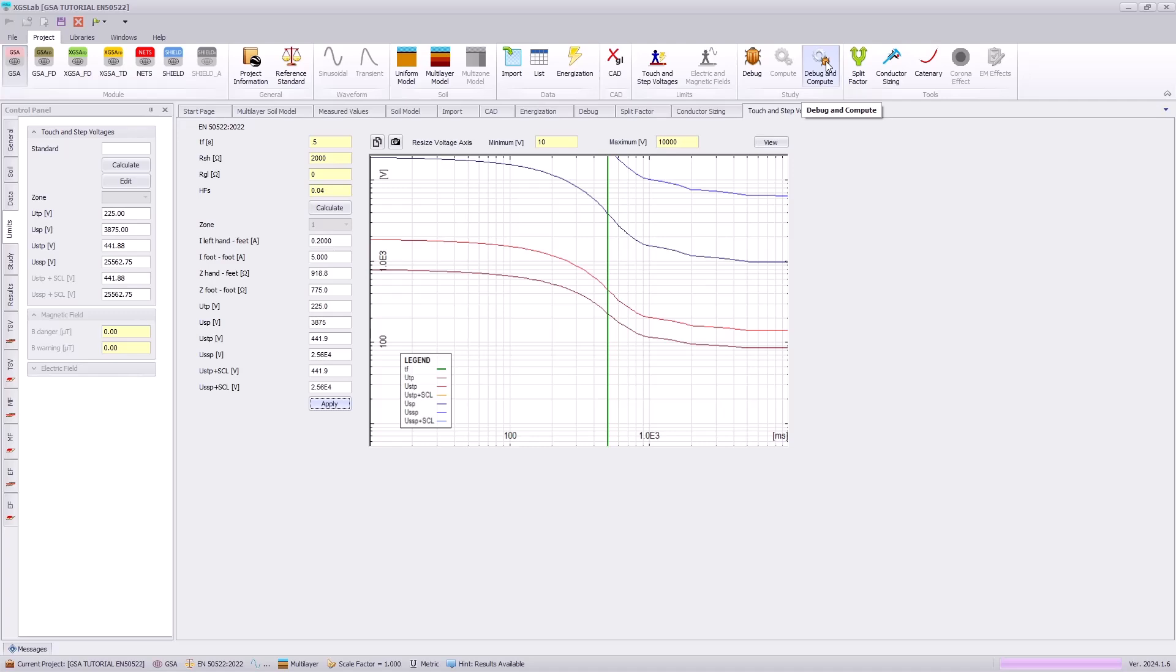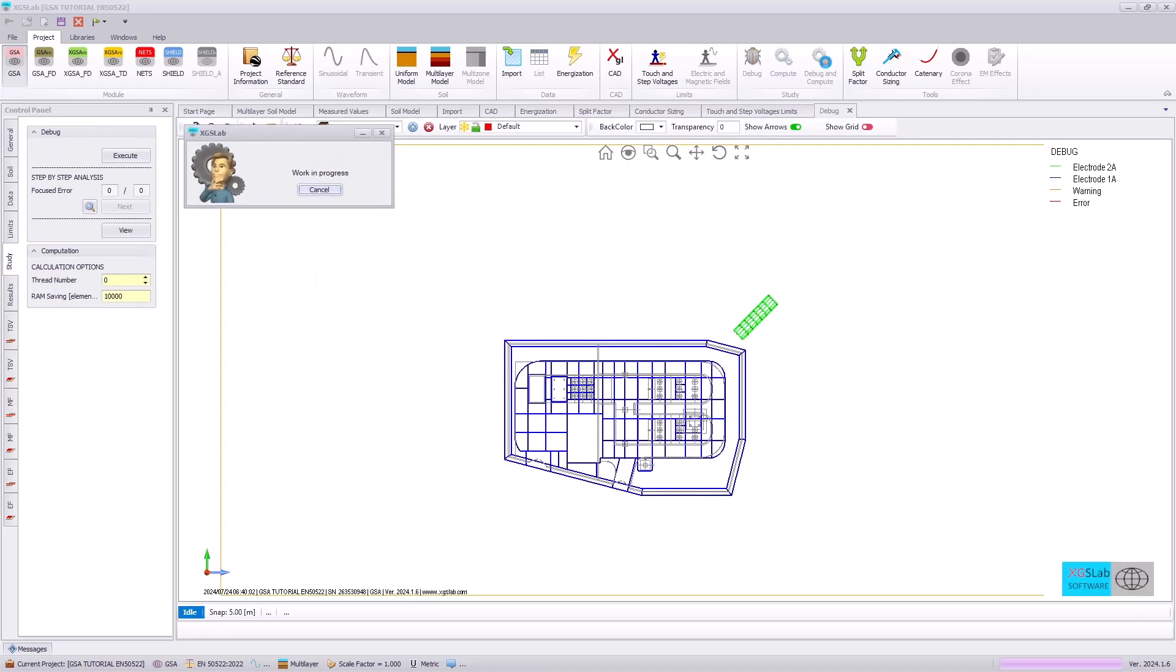Because we have entered in a new energization, we need to hit the debug and compute once again to recalculate the ground potential rise for our grounding system.